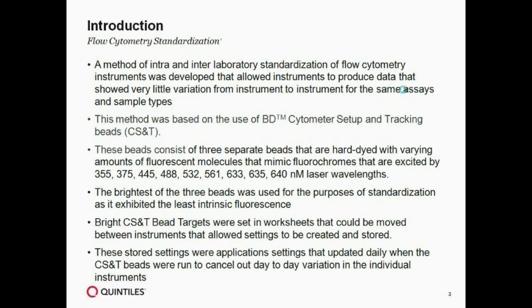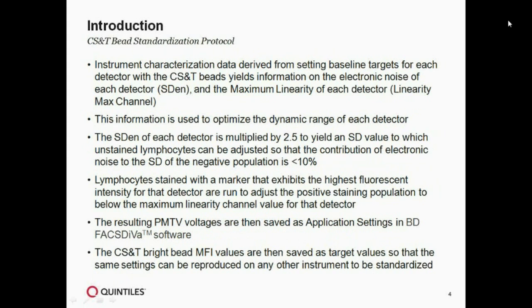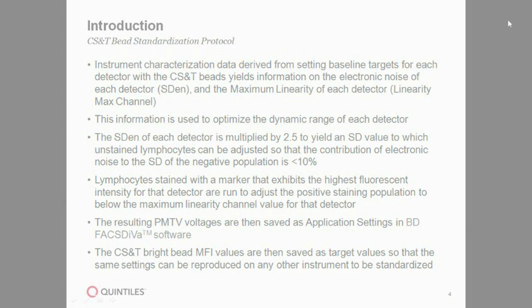How do we set the positive in the same place every day? One of the nice things about running CS&T beads is that the software characterizes the instrument — it tells you a lot about what's going on. The two values we use to standardize are: how much electronic noise there is in each detector, and what's the maximum linearity of each detector. So we're measuring how much electronic noise at the low end contributes to the CV of the negative population, and how bright something can be in that detector before it's off scale and in a non-linear region where compensation is no longer accurate.